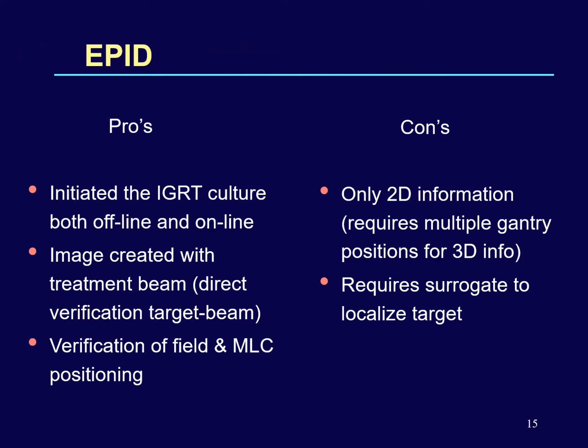The image is created with the treatment beam, allowing direct verification of the treatment, because it is an MV image. Also, if there is MLC shaping, you could see what is being shielded, and with a double exposure technique, you can also see what is outside the beam, what was avoided. The disadvantages were that it only offers 2D imaging, and you have to have multiple beam angles to get 3D information, and it also requires a surrogate to localize the target.